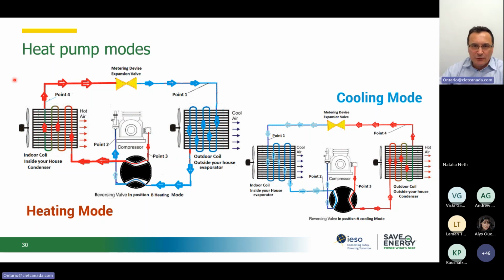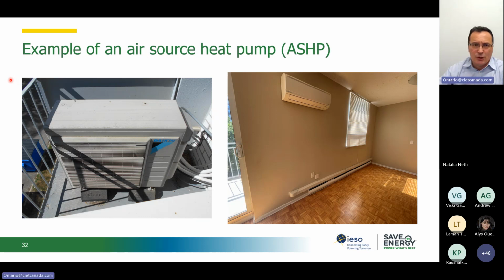I mean, this is something that we see more frequently now. Maybe a few years ago, we would have assumed that this is just a split system for air conditioning. We see how it looks in an installation in a multi-unit residential building. It has one of the two heat exchangers with a compressor outside, and it has the second heat exchanger inside. So again, the two heat exchangers exchange roles in heating and cooling mode. This here will then distribute the air inside the space. It has a small ventilator here that circulates the air for good convection transmission of the heat in the space.